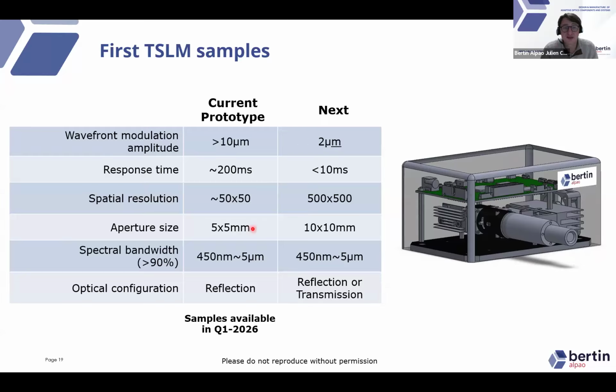Compared to a standard LCOS SLM, we already have a very large spectral bandwidth. So there is no condition on wavelengths within this range, of course, or polarization or monochromatic light. You can use any light you have with the device. And the optical configuration for this device is in reflection. We have to deliver the first prototype to the University of Bern very soon, and we can duplicate it. It's not yet a completely finished product. We call them samples, but they will be available beginning of next year.